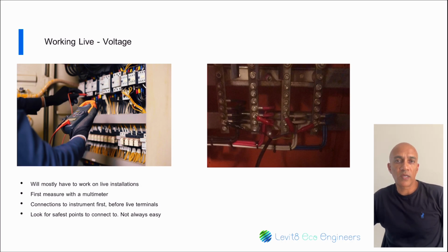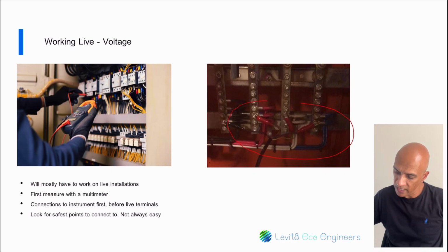Now you are likely to encounter some issues when connecting the voltage and current. For voltage, finding a suitable, secure, safe and solid connection point can be difficult. With most clip-on connections, it is also important to ensure that the connections are not weighed down by the weight of the wires, which could result in the clips coming off at any time. So here's an example that we've discussed previously of connecting to the bolt and nut of the bus bar.